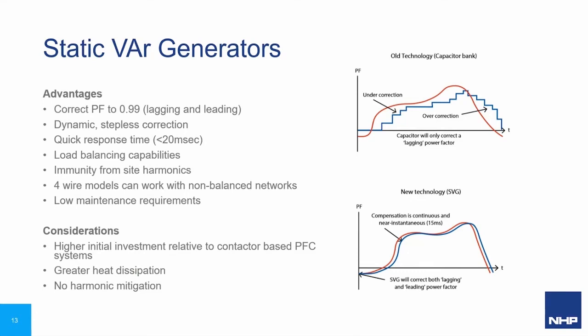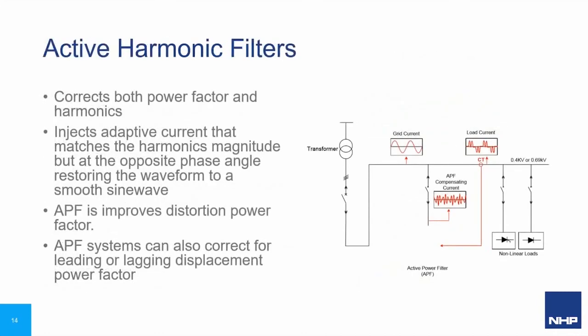Some considerations though to make with static VAR generators: they do have a higher initial investment relative to contactor-based PFC, but we'll talk about that a little bit later. They also do have greater heat dissipation, but they also have additional venting to compensate for that. And static VAR generators are purely there for reactive power, so they do not have harmonic mitigation. But for harmonic mitigation, that's why we have active harmonic filters.